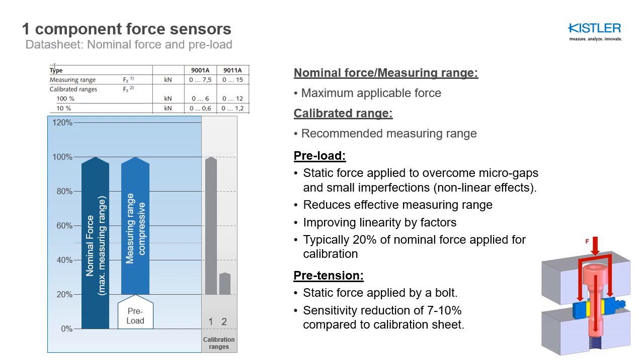This is the normal way to overcome these 20% of nonlinearity when a customer has an application and so on. But as a side effect, you have a force shunt that reduces the sensitivity by about 7 to 10% compared to the calibration sheet. This is not an issue, the sensitivity is still high enough, but you have to be aware of it, since on the sticker of the box where the sensor is delivered, you have different ranges of sensitivity which have a difference of these 7 to 10%, and that's why.